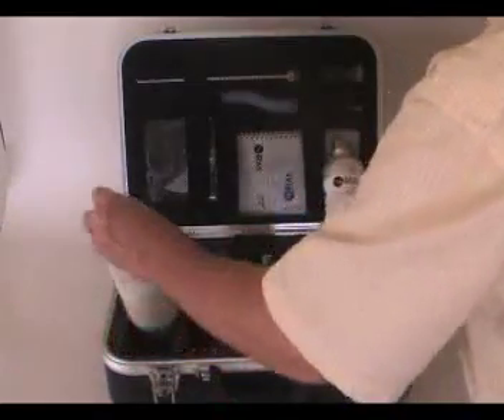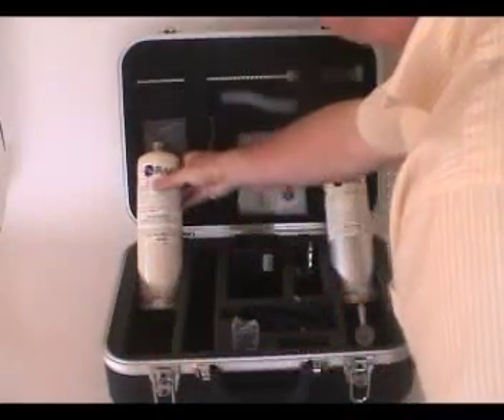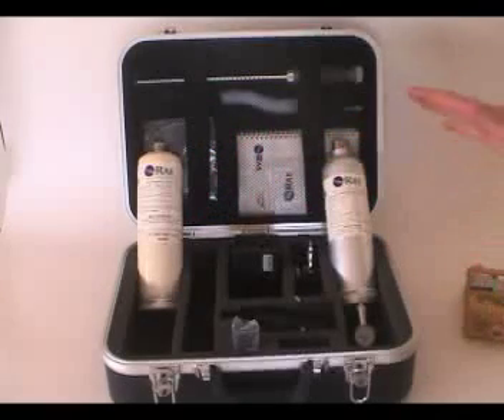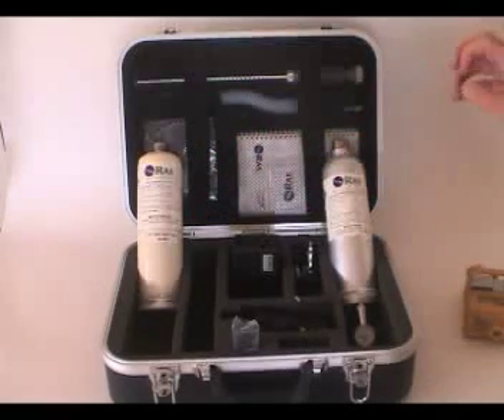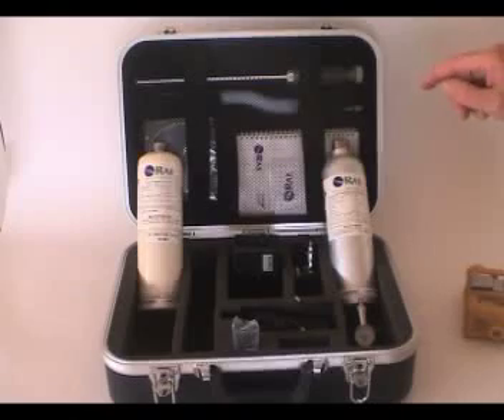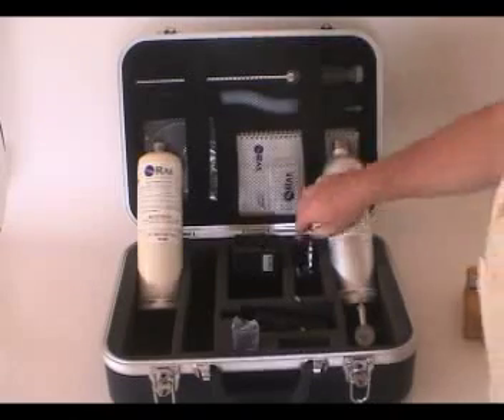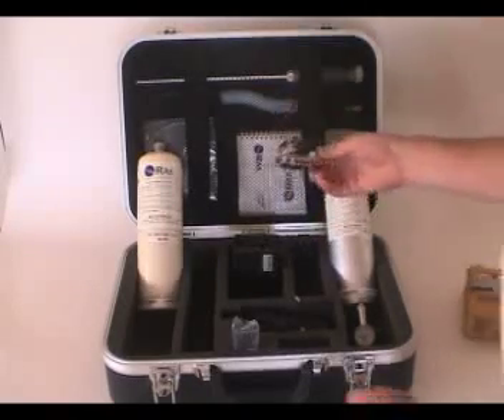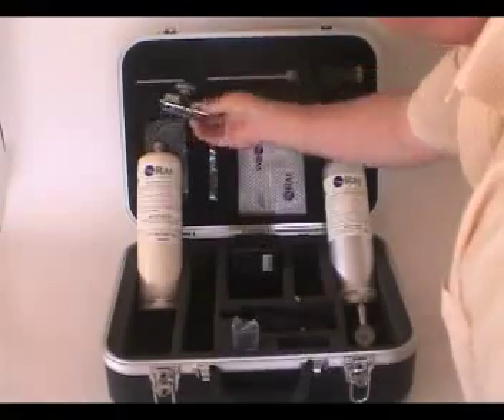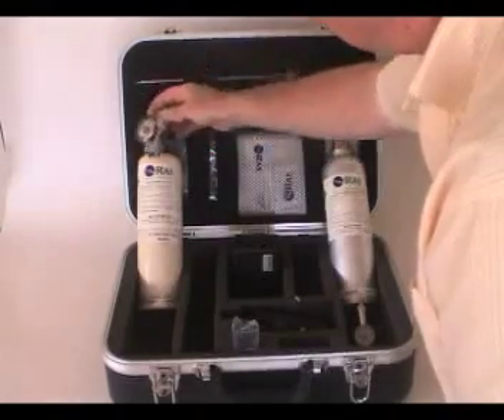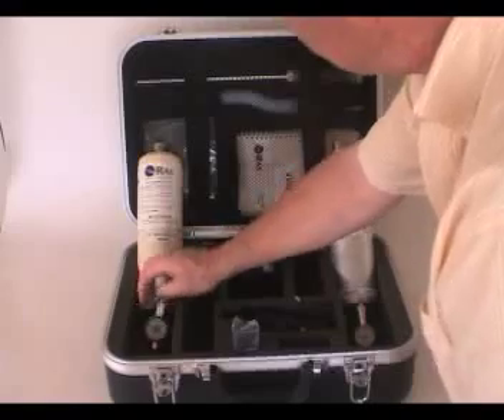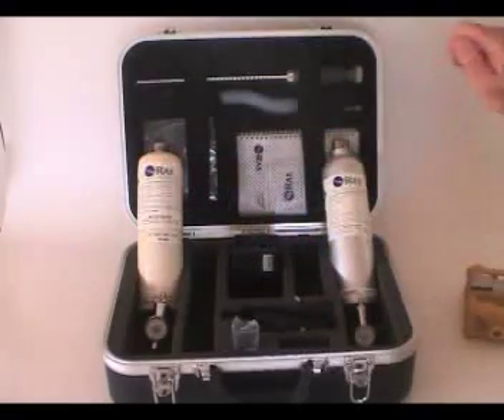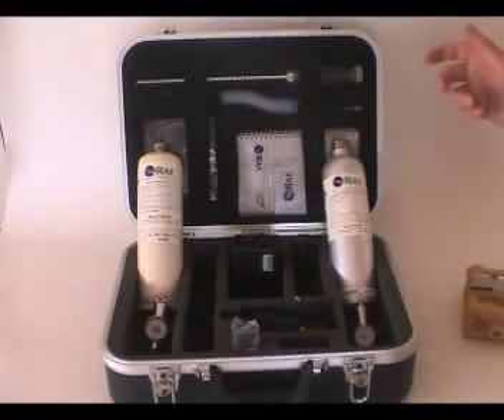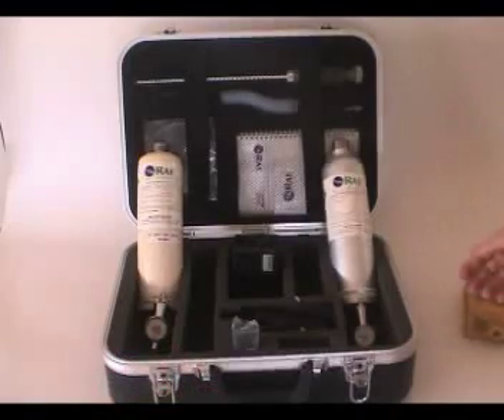Next we have the isobutylene - 100 parts per million. It's a fairly innocuous gas, but it's the standard gas for calibrating a photoionization detector, or PID. We have a regulator for that one too, with male threads on the cylinder and female on the regulator. The regulators have gauges showing how much is in the cylinder, and on-off knobs.